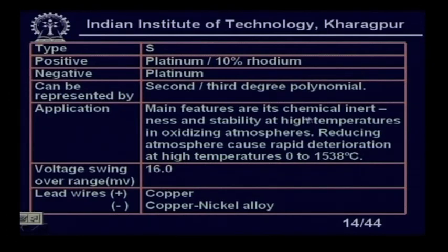Now, the main features are its chemical inertness and stability at high temperatures in oxidizing atmospheres; reducing atmospheres cause rapid deterioration at high temperatures. The typical range should be 0 to 1538 degree centigrade. Voltage swing is 16.0 millivolt.